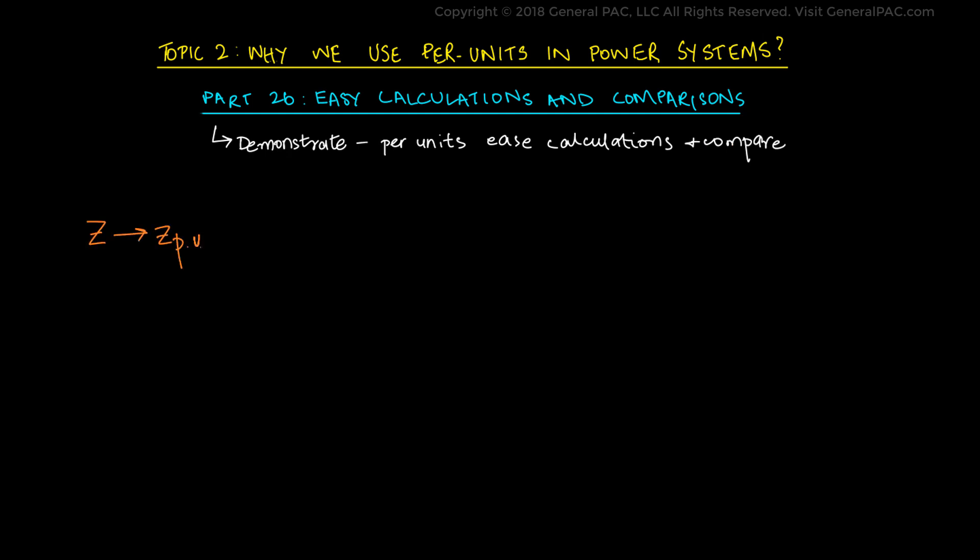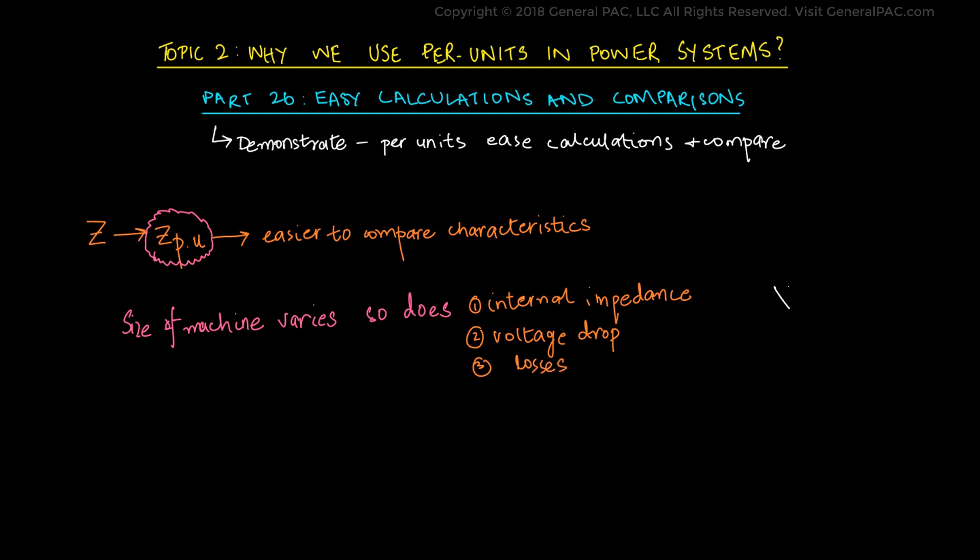By expressing the impedance of different electrical equipment in per units, it is easier to compare their characteristics. We are specifically talking about comparing impedances in per units because the size of electrical machines varies and its internal impedance, voltage drop, and losses also vary. For example, a primary circuit reactance of 0.1 ohms would be much higher for one transformer and much lower for another transformer. The driver for this is the voltage, power, and various other ratings of the two transformers.